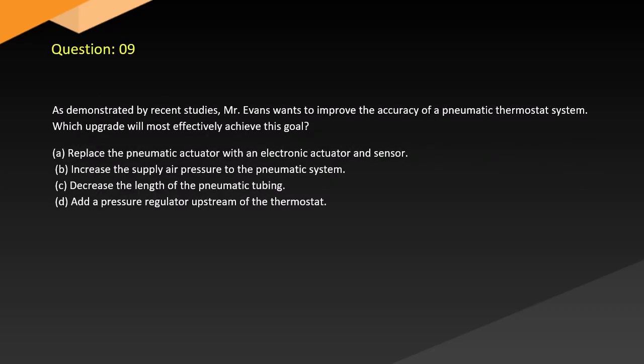Question 9. As demonstrated by recent studies, Mr. Evans wants to improve the accuracy of a pneumatic thermostat system. Which upgrade will most effectively achieve this goal? A. Replace the pneumatic actuator with an electronic actuator and sensor. B. Increase the supply air pressure to the pneumatic system. C. Decrease the length of the pneumatic tubing. D. Add a pressure regulator upstream of the thermostat.